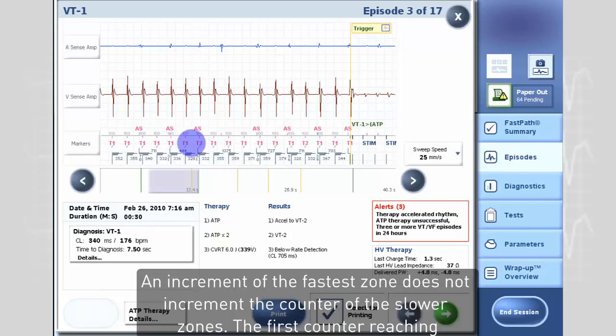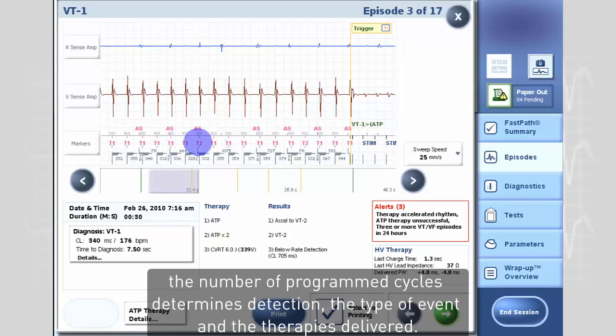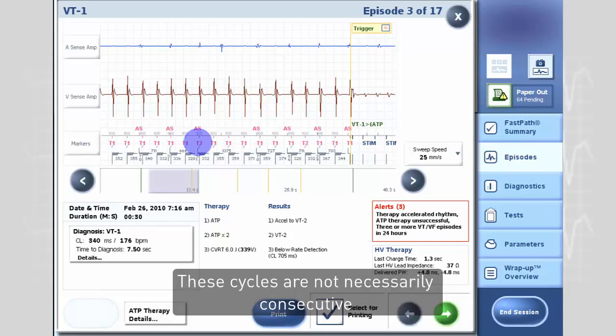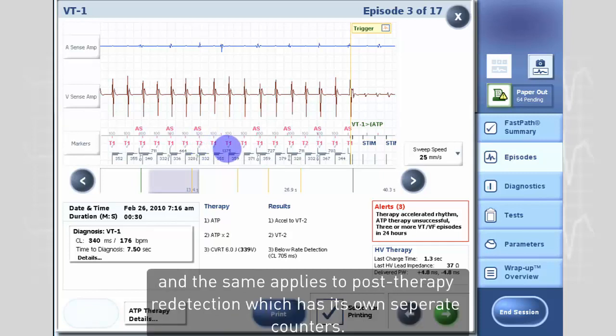An increment of the fastest zone does not increment the counter of the slower zones. The first counter reaching the number of programmed cycles determines detection, the type of event, and the therapies delivered. These cycles are not necessarily consecutive, and the same applies to post-therapy redetection, which has its own separate counters.